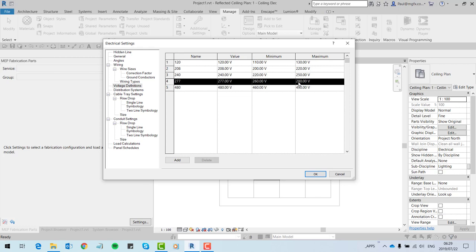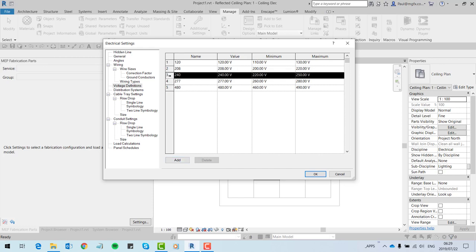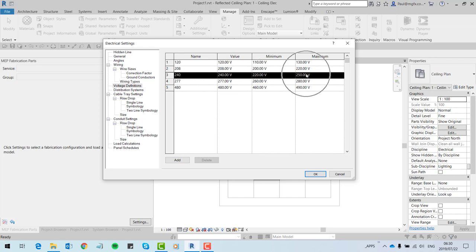We may add voltages or delete them. In this case, there are components placed within the model that utilize the 240 voltage system. We can't delete it, but if it did not exist we could create it or add it. The name: 240, nominal value: 240, minimum value: 220, maximum value: 250. In other words, our lights which have a voltage of 240 are going to fall within this range between 220 and 250. So first things first: define the voltage definition for the components that you need to add to the circuit.